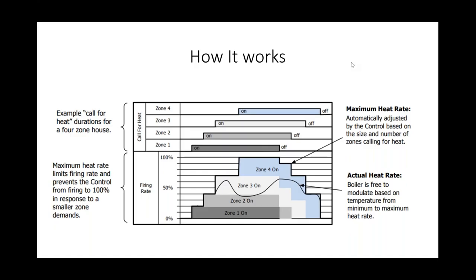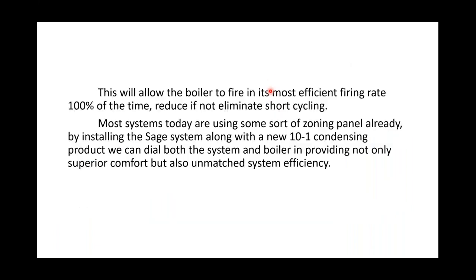We can get whole system efficiency, and this is what this control allows us to do, is take control of that system. Instead of, when zone 1 calls, and zone 1 may only be 20,000 BTUs, it hunting up and down on its curve till that thing's satisfied, it knows 20,000 BTUs is its ceiling, and it stops there. And again, as Megan was saying, it gets the most efficiency out of that product.